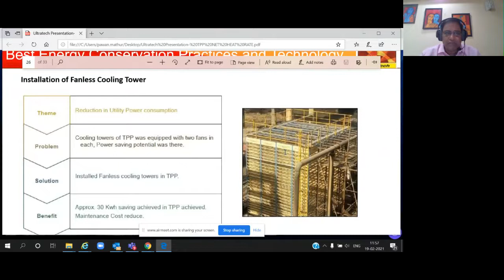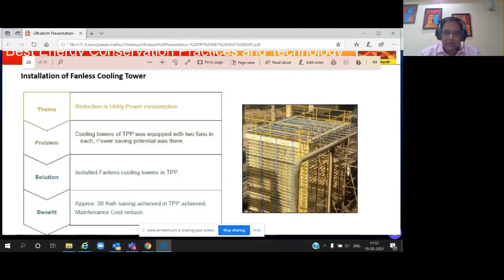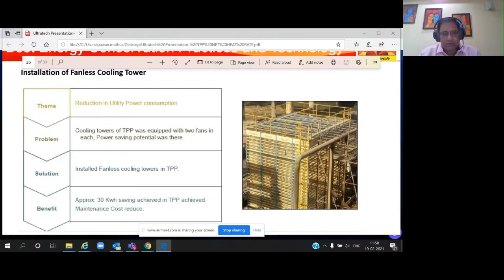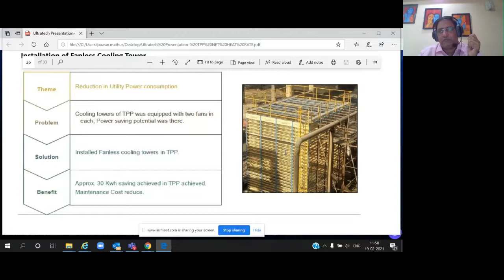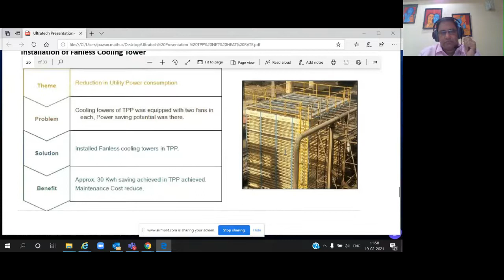We are also installing fanless cooling towers. Fanless cooling towers are proven, where we can remove the fan installed in the cooling tower, saving around 30 kilowatt to 50 kilowatt depending on the capacity of the cooling tower. This uses the gravity method, and these are now commonly available. It also has other advantages: the algae formation that was there earlier is not there because of the construction material used, and it is an almost maintenance-free system. This year we are doing it for around 5 plants. Earlier we had around three plants already done with this kind of cooling tower.